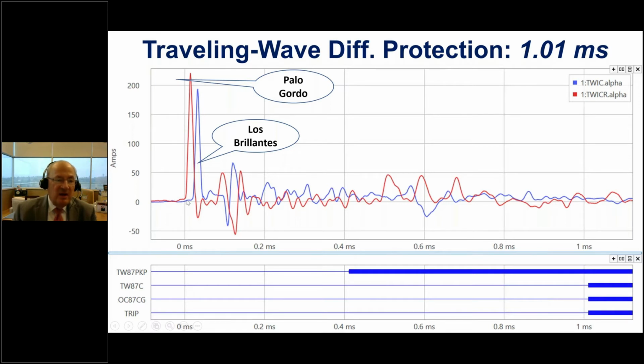So you can see that the traveling waves reach the two substations at slightly different times, measured really in microseconds. This is 200 microseconds now, so maybe they got to the two ends of the line only about 30 microseconds apart. So if the fault had been right in the middle of that 18-mile line, it would have reached the two ends at exactly the same time, and those peaks would have overlapped perfectly. So you can even tell here that the fault was a little closer to one end than the other.